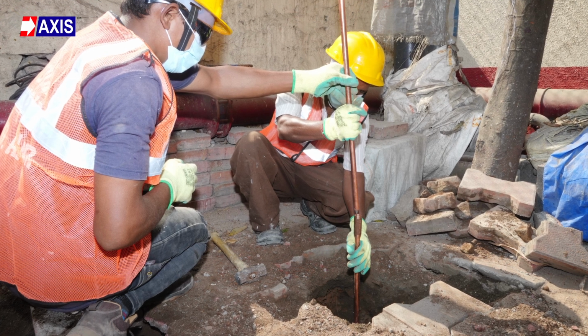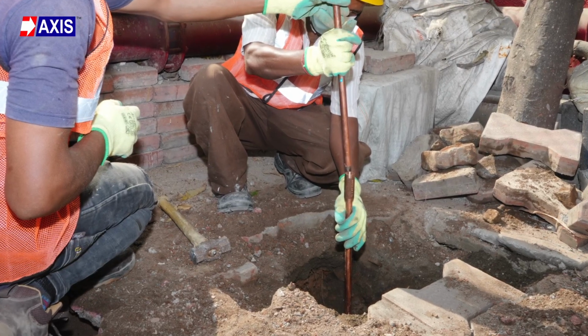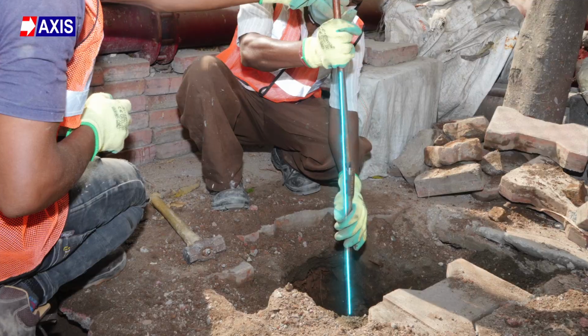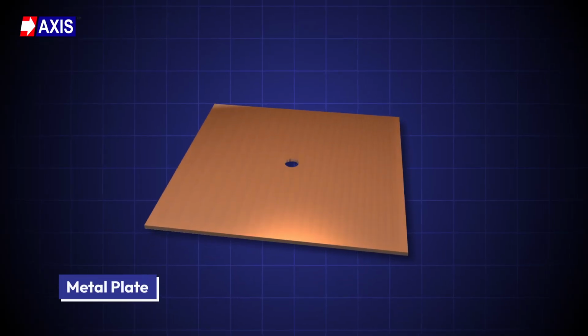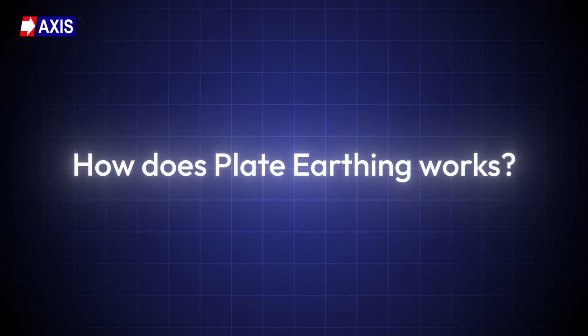There are different types of earthing systems like plate earthing, rod earthing, strip earthing, and pipe earthing. The shapes are different, but the job is the same. Each one takes fault current safely into the soil. To do this, every system needs a metal piece buried in the ground, and this buried metal piece is called an earth electrode. It is that part of your earthing system that actually touches the soil and carries the fault current away from your equipment. In plate earthing, this electrode is a metal plate. So let me explain how plate earthing works.